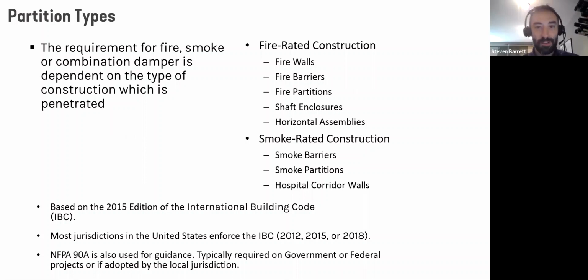So what you all came to hear, different partition types. This is really important because you all said it depends on the answer to that question, right? The requirement whether or not you need a smoke damper depends on what type of construction is being penetrated. It's not simple enough to say, well, it's 1 hour, so I don't need a damper, and if it's 2 hours, I do. That's not true. It's an oversimplification, and that could lead to some of the errors we talked about at the beginning, of either over-specifying dampers when you don't need them, or even worse, missing one and having a potential life safety issue.